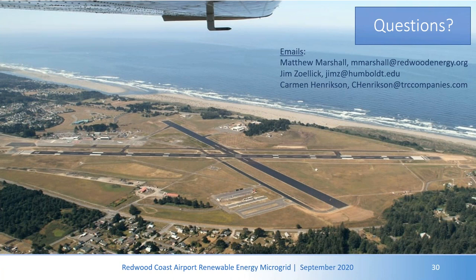In terms of the behind-the-meter system, the NEM system, that's just a standard net metered system. There's a SCADA control breaker on that system. Because we could have a situation if the battery was fully charged and the loads were rather low on a full solar day—the peak load on that circuit is about 330—so if the load was kind of low, say 250, and the PV system's producing 300, and the battery's full, that's a problem. So we will have the ability to curtail that system if needed, but only in the case where there's too much generation on that circuit and you've got to curtail something, otherwise everything's going to shut down.